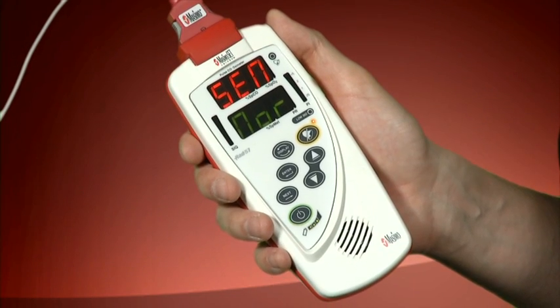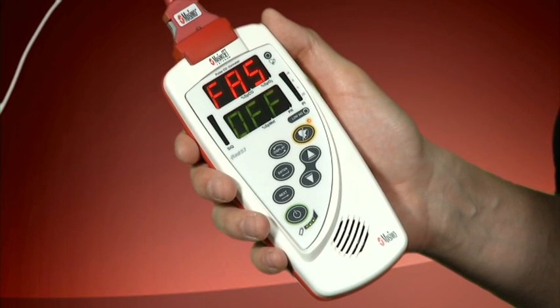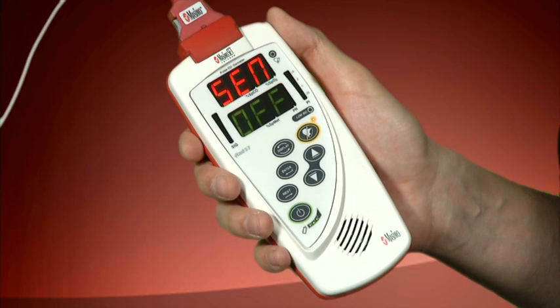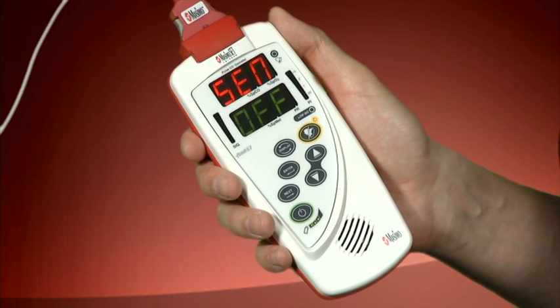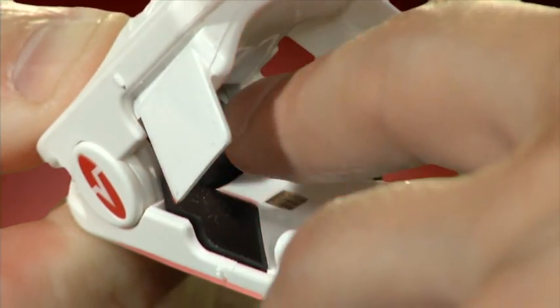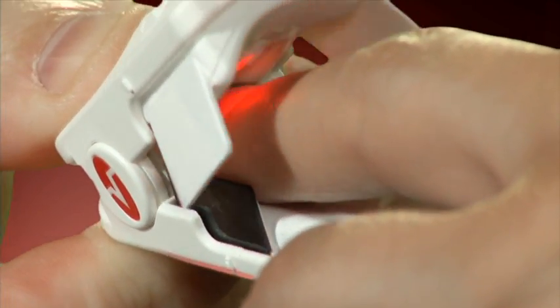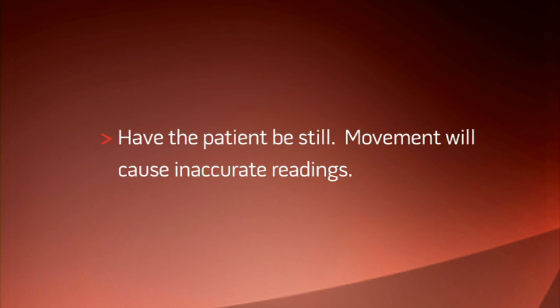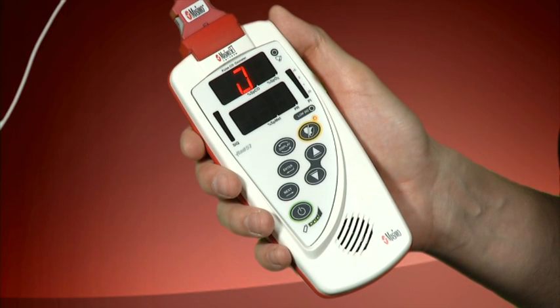Each time the device is powered on, it will run through this self-test. When the display shows SEN off, meaning sensor off, the device is ready. Insert the patient's finger into the sensor, making sure to follow the proper techniques. Have the patient be still. Movement will cause inaccurate readings. Now the Rad57 will calculate the measurements.